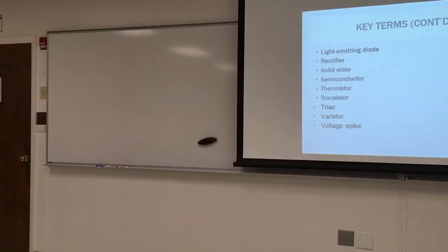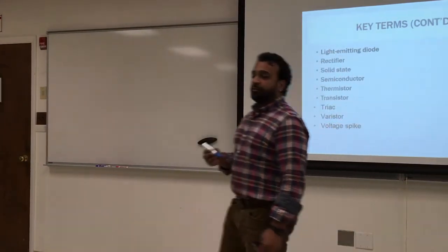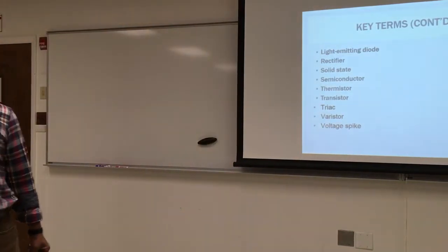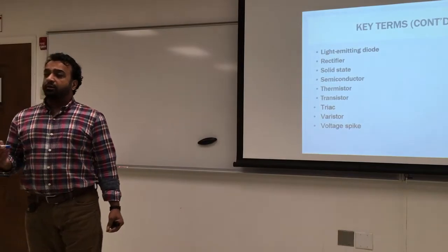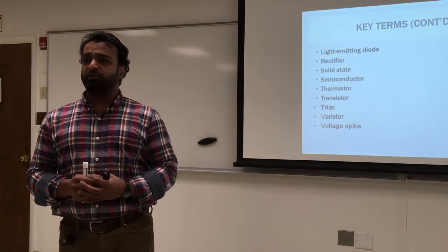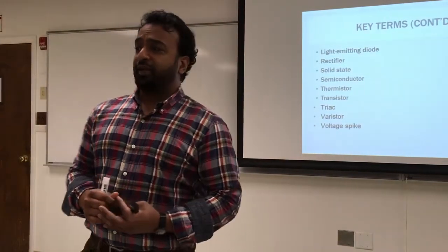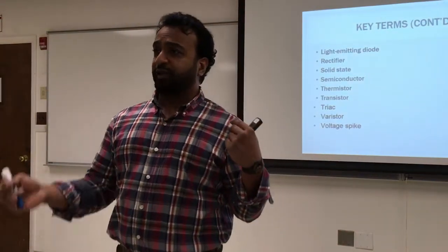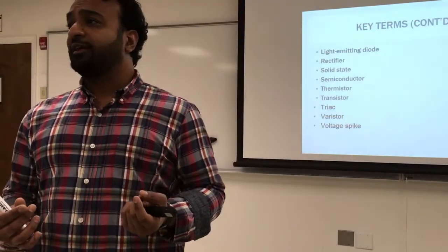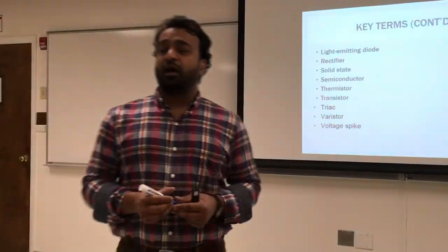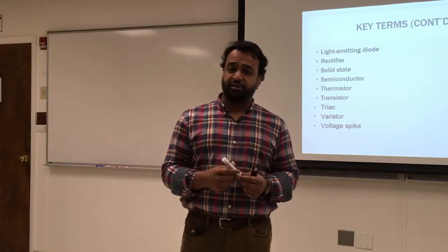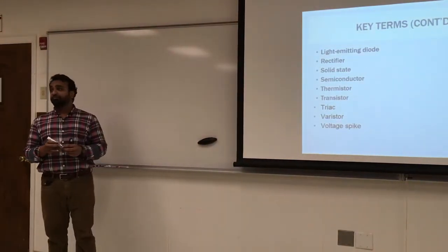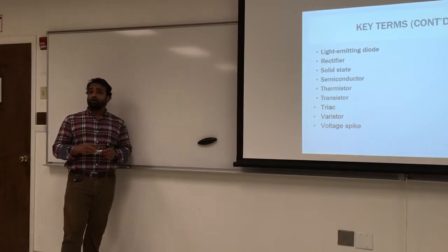I want to spend a little bit of time on that because this will be the basis for flame detection systems, which means what? There's something in the industrial world called the flame rod. And the flame rod is basically a rectifier. You run AC to it, and through the flame, you change AC to DC. It's kind of like magic, but that thing actually became a turning point in flame detection systems. How does it do that? This is very, very oversimplified. It's not completely scientific. I'm not going to go through all the science behind it.